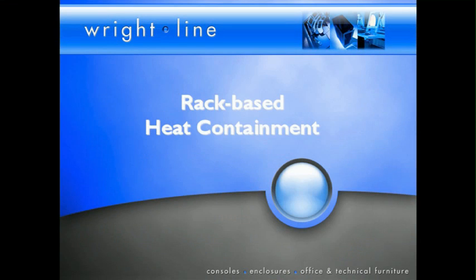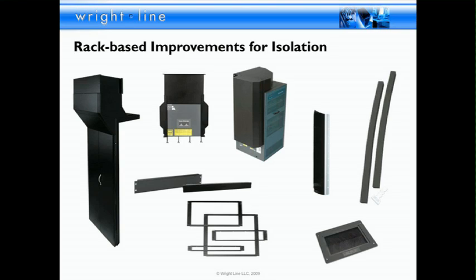Rack-based heat containment. When you start getting into the rack, this is the area of your data center where you try to set up a barrier, cold to hot. It's very important that good rack hygiene is taking place. A variety of different products exist in the market around sealing that front to back barrier, and obviously the blanking panels make a big difference.